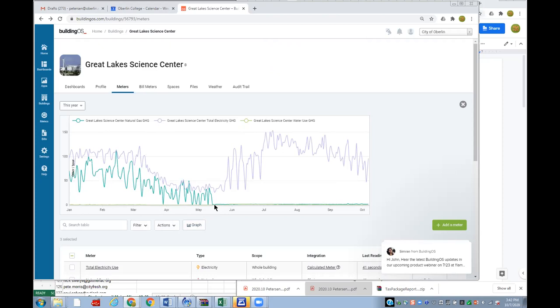And that's two things going on there. One is you're at the end of the heating season, but the other thing is you closed down the cafeteria, which uses natural gas. And they evidently really have basically yet to turn it on because there's almost no gas use even till October at this point. I think normally you would have seen it throughout the year because of the cafeteria use, but it's obviously related to heating, which is interesting and important.